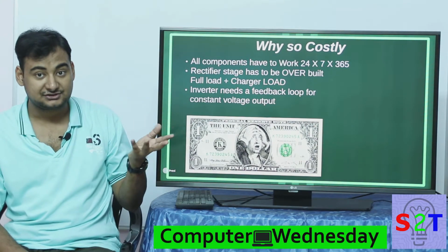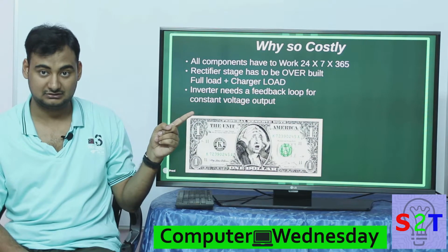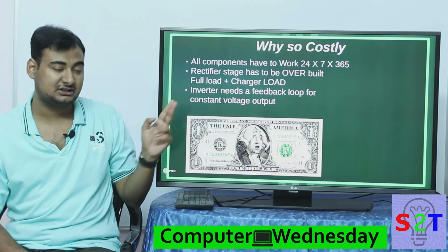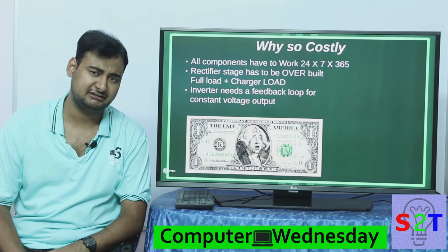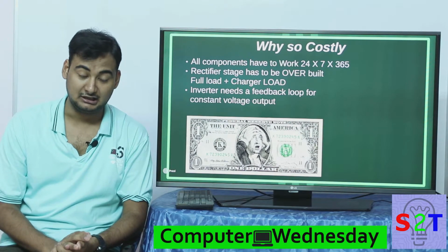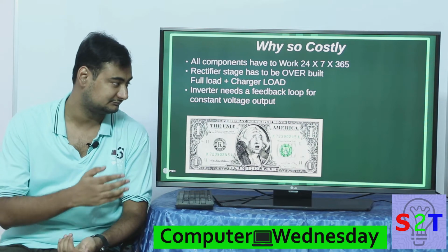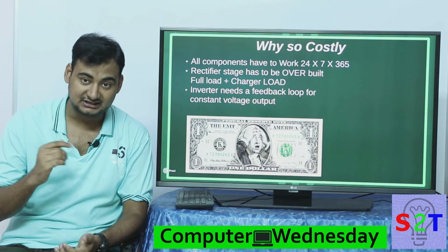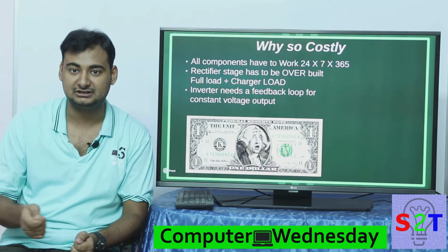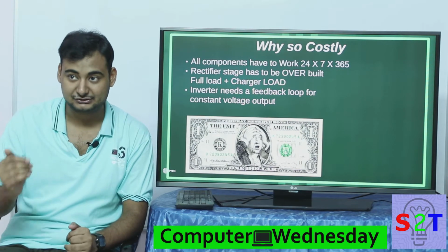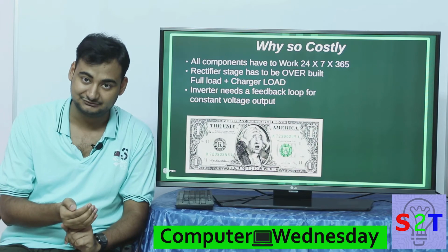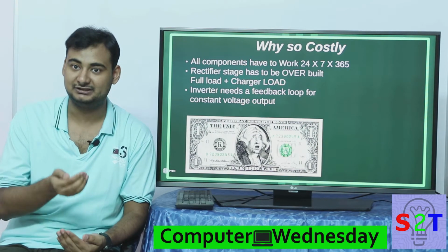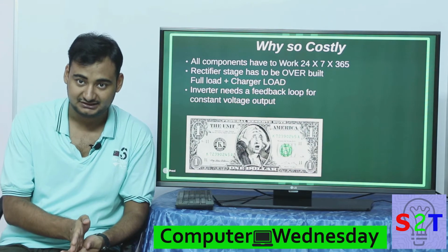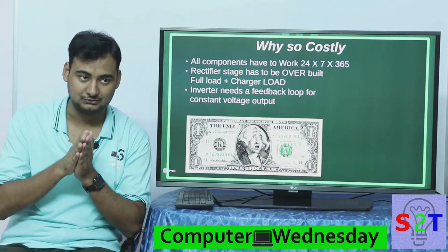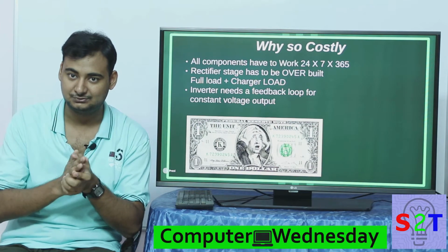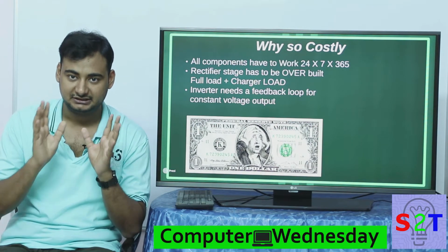And the rectifier also has to be overbuilt. It's like full load plus the charger load. And the inverter also needs a feedback loop. Generally sine wave ones have it, but it's also compulsory for an online UPS, because without a feedback loop, the pulse width modulation cannot be controlled properly. So it cannot guess. It has to know the voltage that it is sending out. Let's say it's 220 volt. It has to be 220 volt. It cannot be 210 volt or 230 volt. It has to be 220. And they will generally give you a very tight range. So you don't need any stabilizer or CVT or anything for your products.